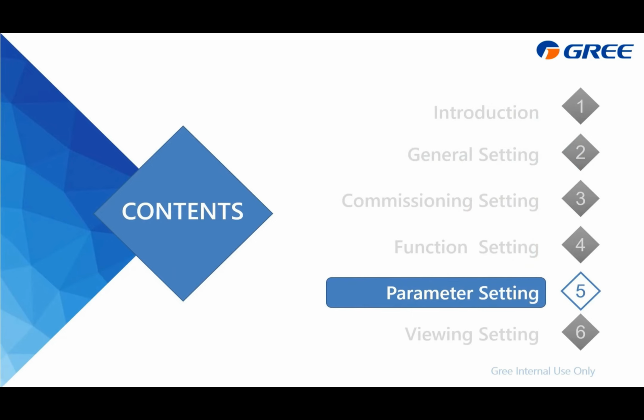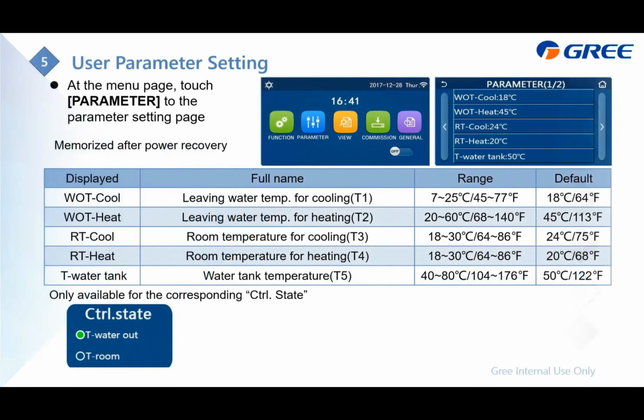Parameter setting. Next, we will go to the parameter setting, which is from here, and then we will go to this page. Actually, it is this table. What you can change is the water out temperature for cooling and heating, and also you can select the room temperature for cooling and heating. But for this one, you need to be equipped with the remote sensor. And the last is the water tank temperature. All of these are the setting targets. And also, if you would like to select this RT, you need to change the control state to be the T room.